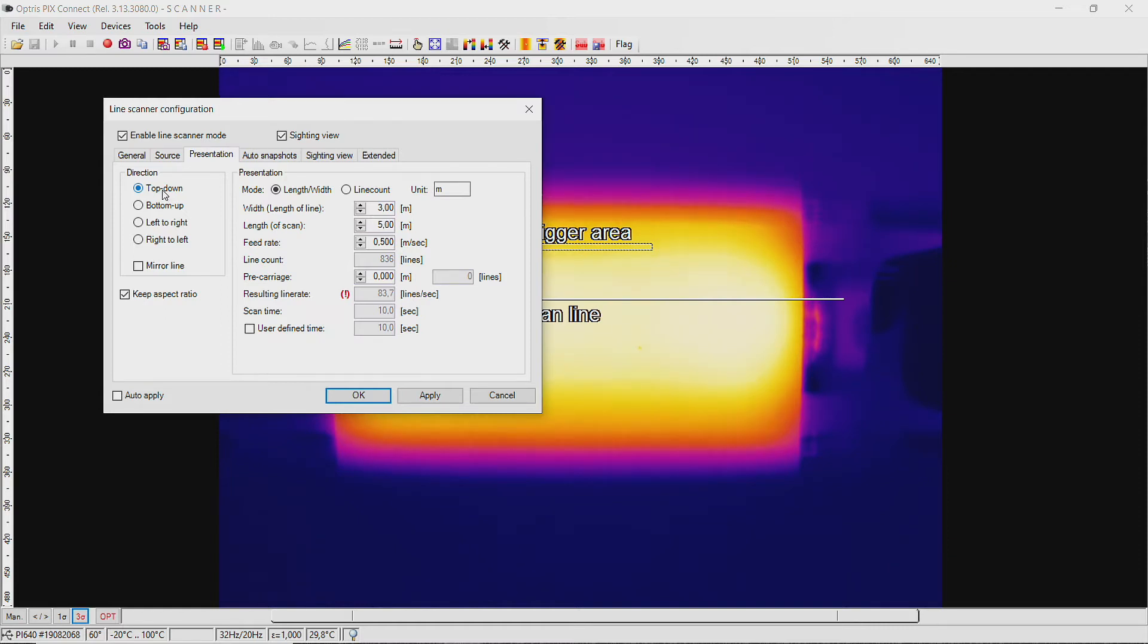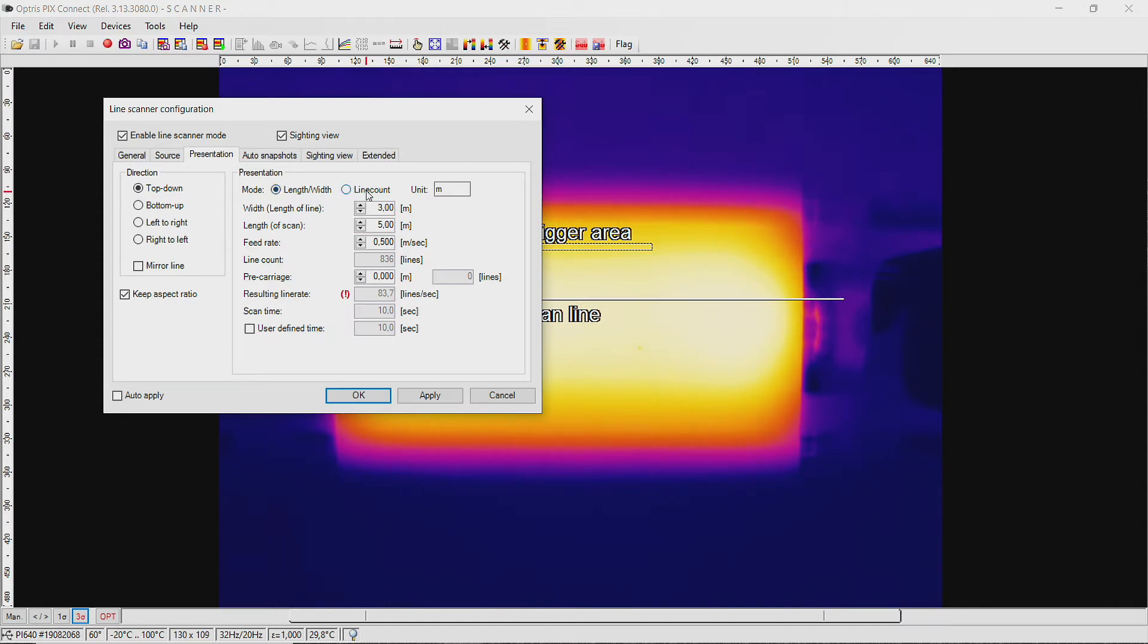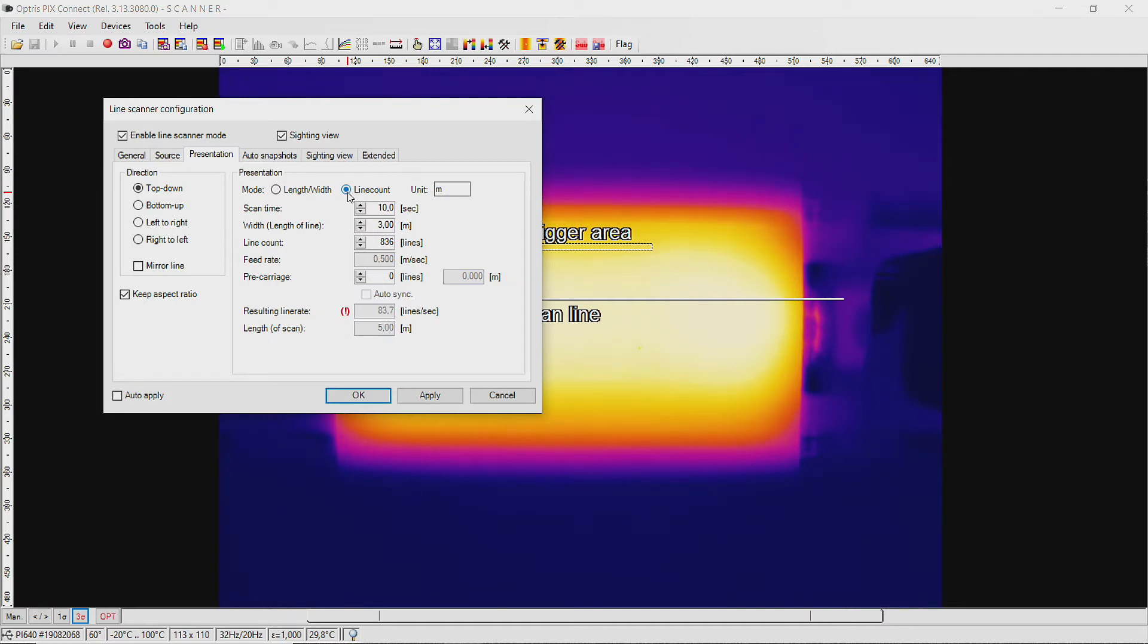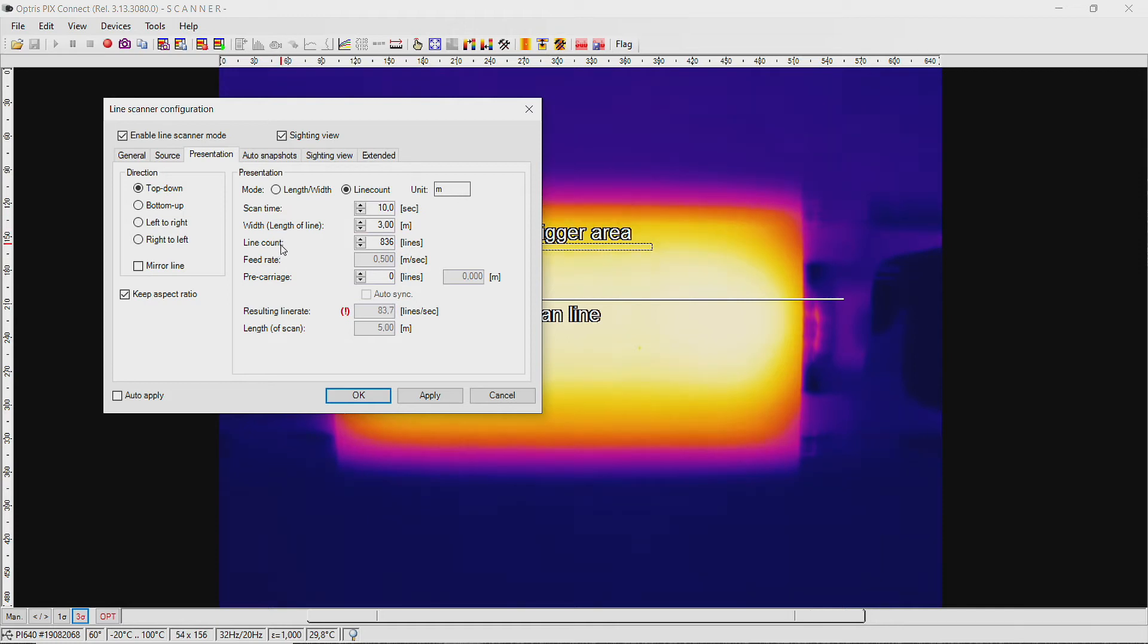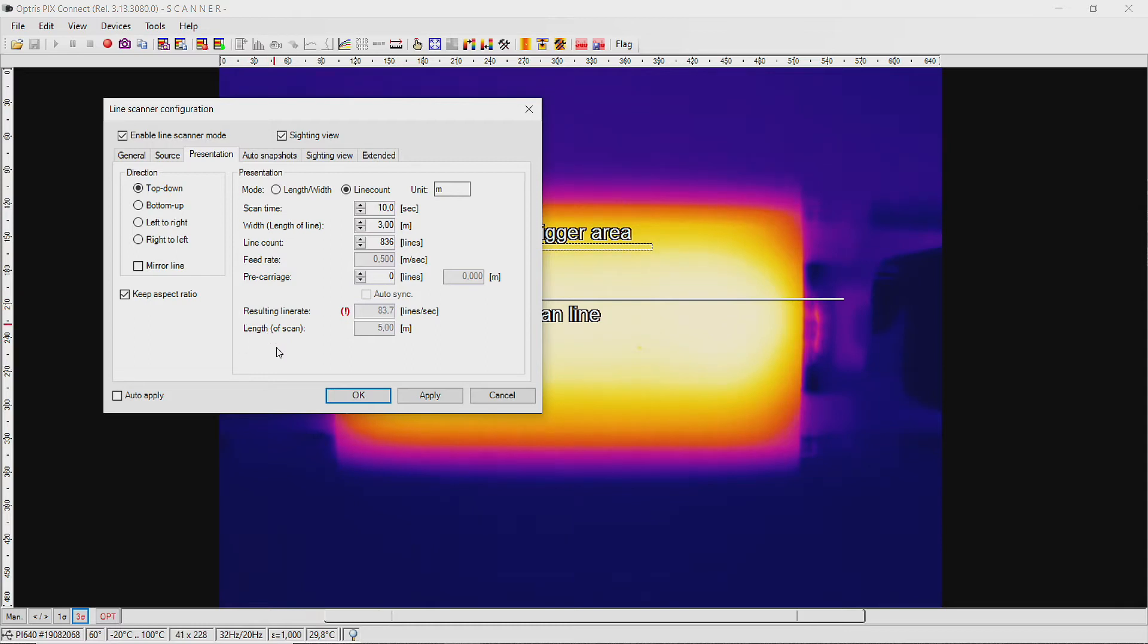Now you can decide if you want to use the length width presentation mode or the line count presentation mode. Let's start with the line count presentation mode. At this mode, the display of the line scan is done by the scan time and the line count. Here you can decide how many lines have to be scanned and in which time. The resulting line rate should correspond to the maximum image frequency of the used camera.